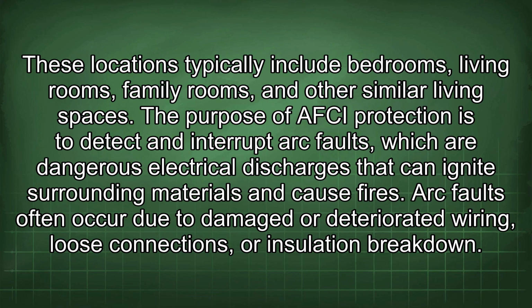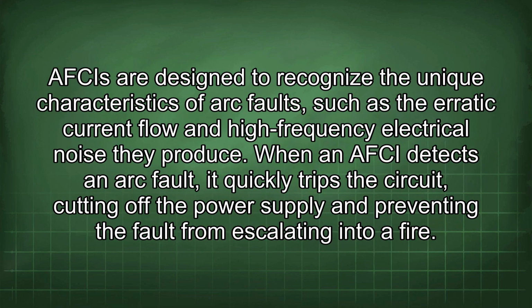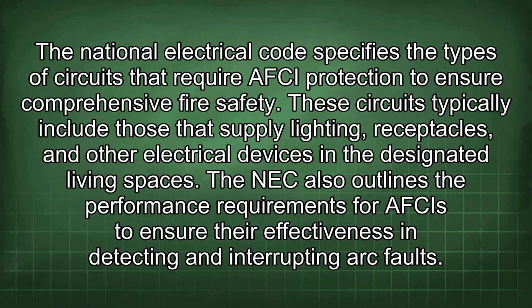Arc faults often occur due to damaged or deteriorated wiring, loose connections, or insulation breakdown. AFCIs are designed to recognize the unique characteristics of arc faults, such as the erratic current flow and high-frequency electrical noise they produce. When an AFCI detects an arc fault, it quickly trips the circuit, cutting off the power supply and preventing the fault from escalating into a fire. The National Electrical Code specifies the types of circuits that require AFCI protection to ensure comprehensive fire safety. These circuits typically include those that supply lighting, receptacles, and other electrical devices in the designated living spaces.